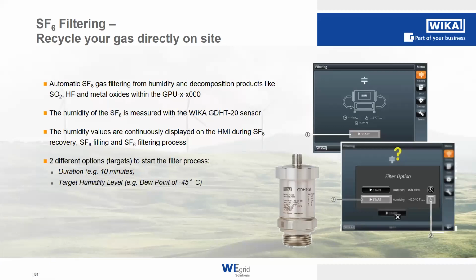As with the GAD, you also have the function with the GPU that you can recycle your gas. Therefore, it is possible to either set a certain recycle time, meaning you can set the cycle internally for 10 minutes. So the gas will be dried for 10 minutes running through our humidity filter. And after that, you get the info on how much the dew point has improved. But you also could set a target humidity level, like a temperature for the dew point, and then start the process until this value is reached.